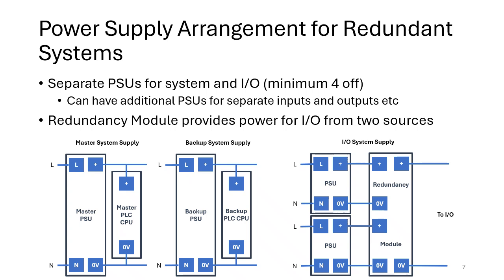So the way we do this now is we still have 2 power supplies, but now we have an additional redundancy module. And what the redundancy module does is it takes in the 2 power supply inputs, and then it provides adequate power supply to the I/O modules from those 2 sources. So we'd need to supply a power supply which is capable of driving all the I/O. So for example, that might be 10 amps, in which case we'd need two 10 amp power supplies. The redundancy module then would need to have a current capacity which matches the power supply in order to be able to supply that same amount of power to the I/O modules.